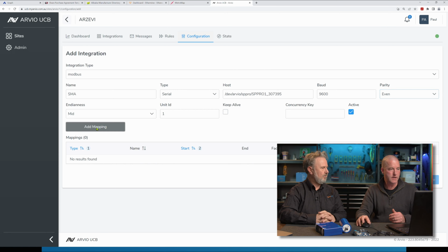Yeah, it's very flexible. So then you add a mapping. Once you've found the device, when you buy a product that has Modbus, it'll give you a Modbus map, which says on line 105 you'll find voltage, on line 106 you'll find energy. So you just go in here and add mapping.